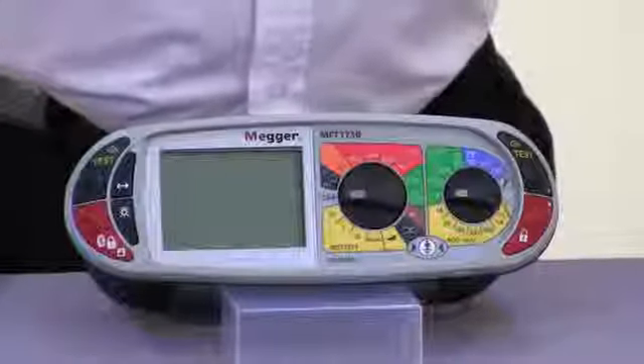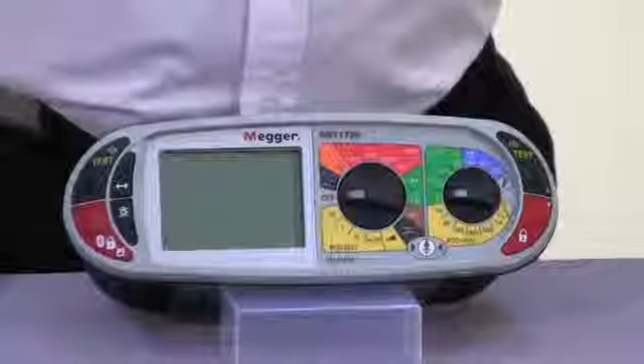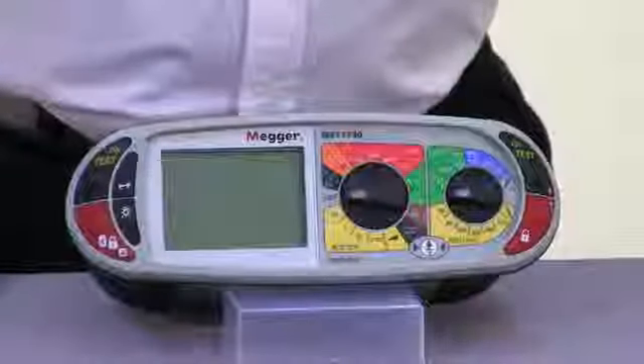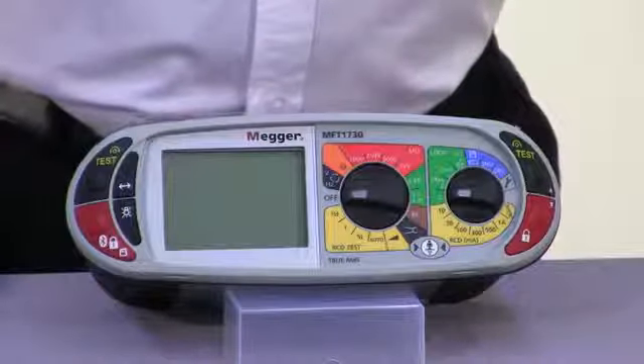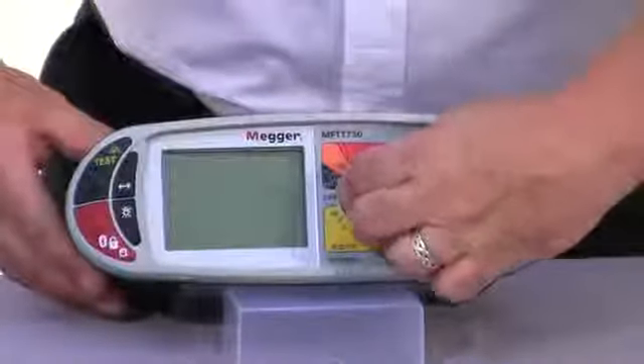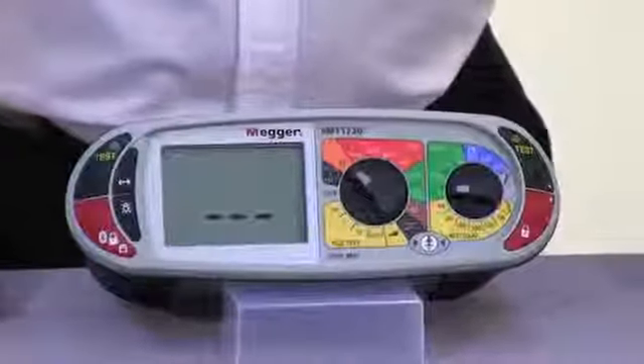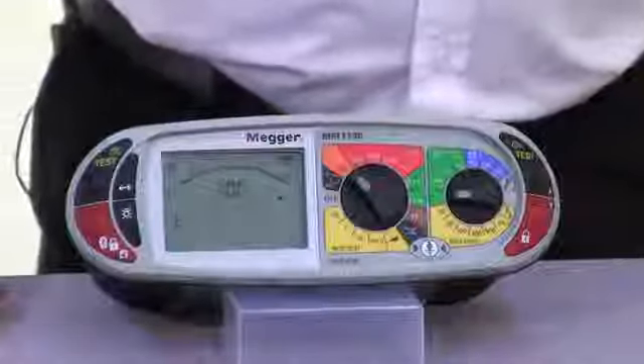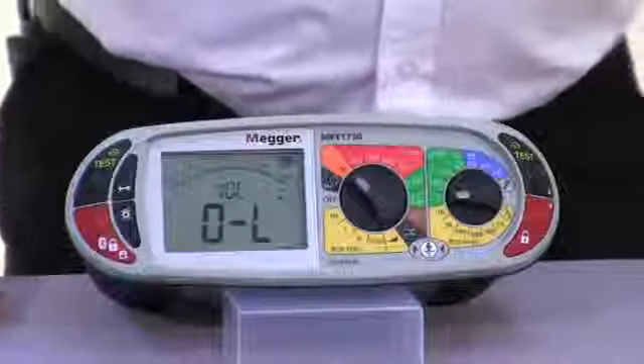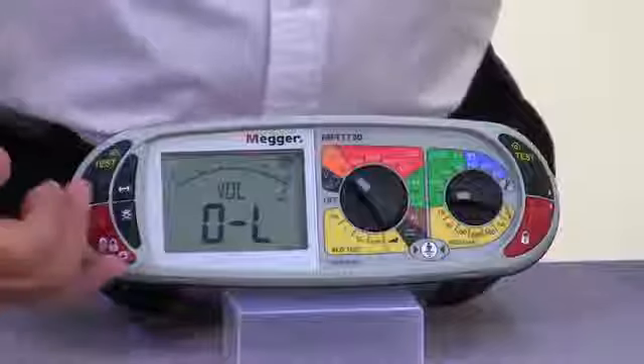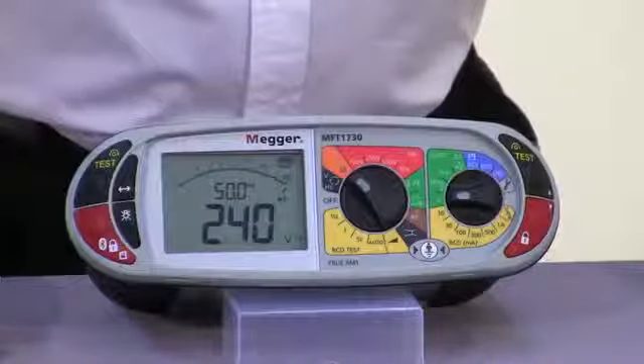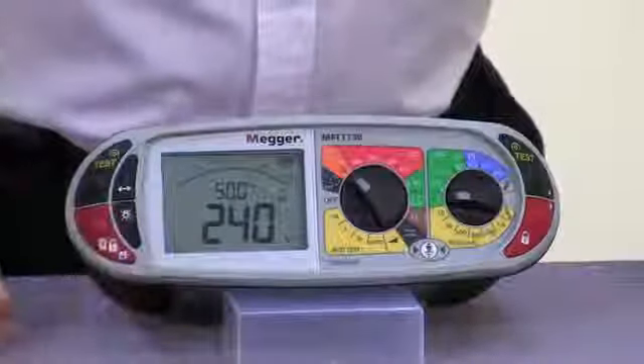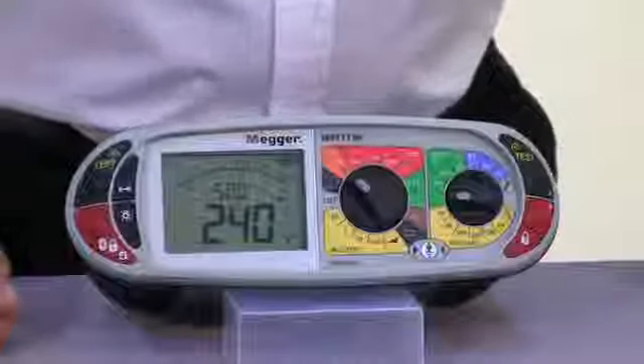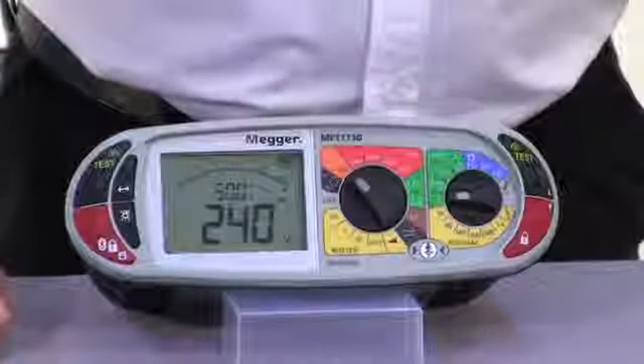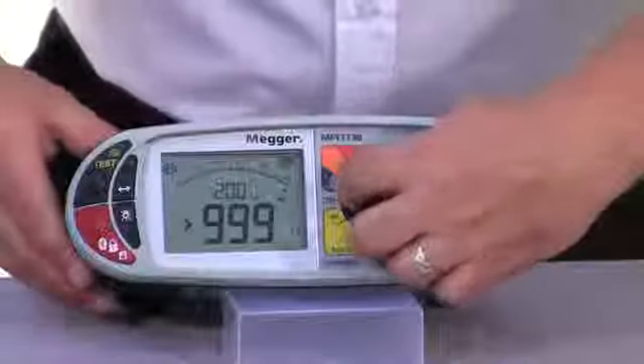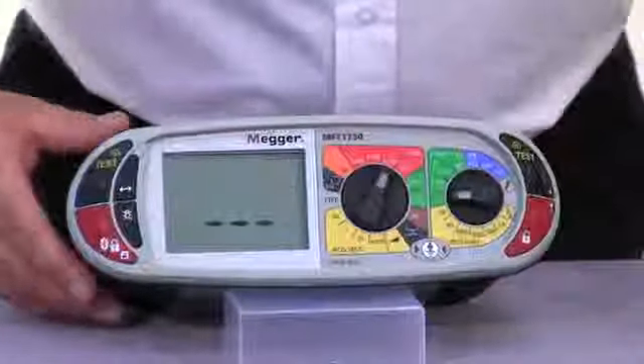At this point, what I'd like to do is just show you the input protection that's built into every model of the MFT1700 series. So if, for example, we were selecting one of our dead tests, whether it be continuity or insulation tests, and we accidentally apply a voltage, you'll see straight away we get an indication on the screen, you get an audible indication, and then the unit will click over and actually indicate the voltage that you've attached the probes to. This is exactly the same when you're carrying out an insulation test.